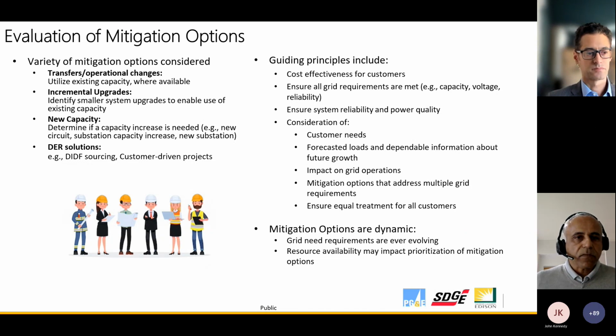A lot of times, one project can solve all those needs — providing capacity, maintaining voltage, and providing reliability for customers. Sometimes we may have a need at one substation, but to solve it we actually increase capacity at another adjacent substation because it's more cost effective. That lets us move the load around and take care of the need from a completely different substation than where it shows up. So people may see a circuit overloaded on one substation, but the project is at a different substation. We do that — we look at the overall most economic, cost-effective solution, and sometimes that solution is somewhere else, allowing us to transfer load to take care of the need.